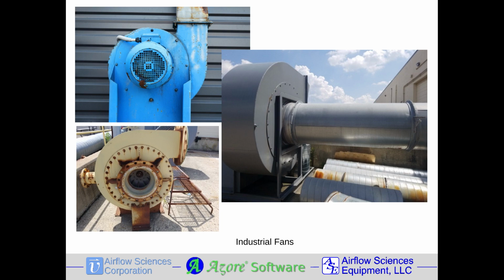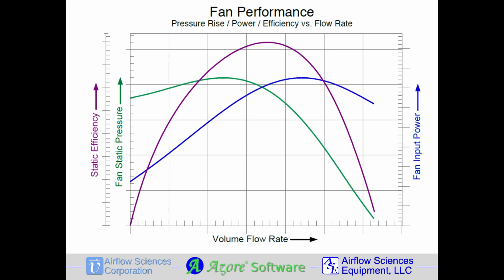One of the more common devices in industry, how your fan is operating can relate to many of the perplexing woes plants face. Poor evase design, duct design, inlet conditions, or vanes can cause serious, costly, and sometimes dangerous problems. Fans move air or gases at a constant volume. The higher the density of this medium, the more energy is required to move the volume at a given RPM.